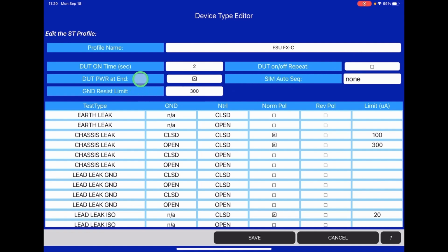Next field is DUT power at the end. We enable this so that power stays on the electrical safety analyzer to the ESU at the end of electrical safety test, in case we want to do some more functional tests. Simulation auto sequence, you could program these. We're doing an ESU, so it's not necessary.